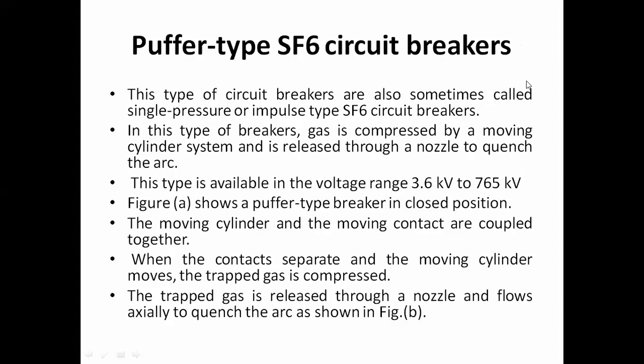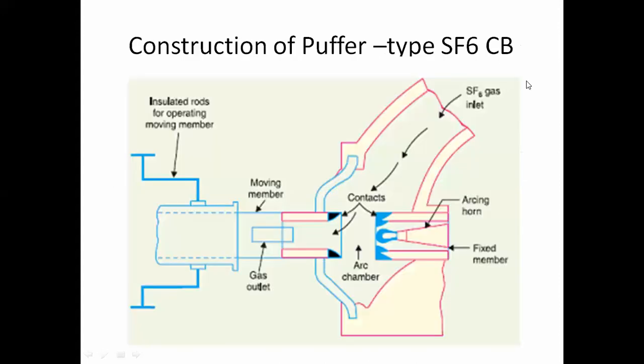So if you see, this is the construction of the puffer type SF6 circuit breaker. On the left hand side, the blue part is the moving contact chamber, with a moving member, and on the other side the pink part is the fixed contact. When there is no fault in the system, the moving contact, the moving member, and the fixed member are closely coupled to each other.